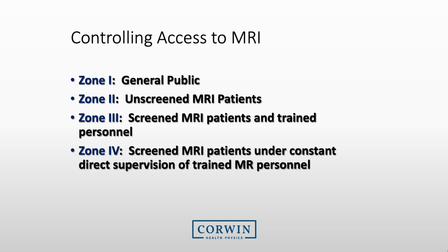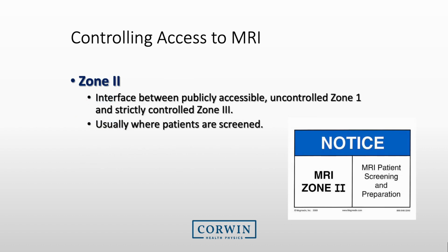Since we have a strong magnetic field present, we restrict access to areas in MRI facilities by creating zones. The 4 zones are listed here, and we will go into detail with each of these zones. As noted on the previous slide, Zone 1 is the area for the general public. Zone 2 is typically the area in which the general public is interviewed and screened before entering Zone 3. Zone 2 is also populated by staff that may not be trained in MRI safety.